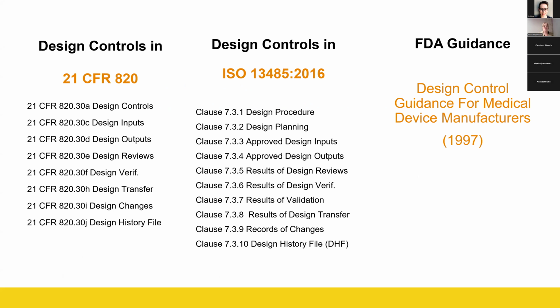So, talking about these three things: design controls in the federal law, design controls in ISO, which is an international standard organization, and then the FDA guidances. These are the three main areas where you're going to find information on how to do design controls. So the Code of Federal Regulations, ISO 13485, and a document that's still up. The latest document was from 1997.